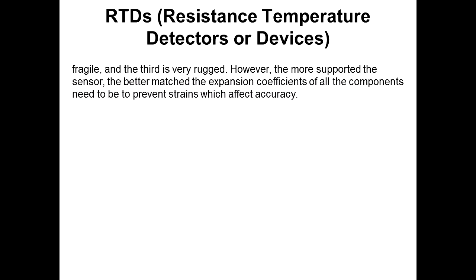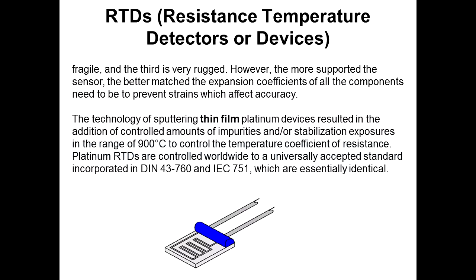However, the more supported the sensor, the better matched the expansion coefficients of all the components need to be to prevent strains, which affect accuracy. The technology of sputtering thin film platinum devices resulted in the addition of controlled amounts of impurities and or stabilization exposures. They sputter molten platinum onto usually a little ceramic chip, and then they laser cut it to trim it to get the proper resistance levels. And these are good up to about 800 to 900 C and are used throughout industry because they're much more rugged and vibration proof than wire wound RTDs. And these are built to either the DIN 43760 standard or the IEC 751, which are pretty much comparable.